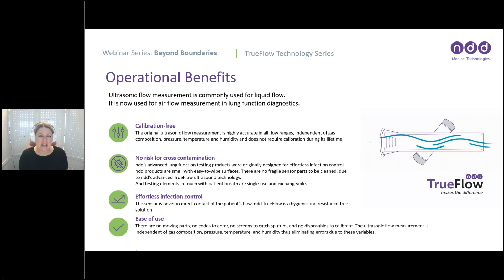There's also no risk of cross-contamination. NDD's advanced lung function testing products were originally designed for effortless infection control. They're small portable devices with easy to wipe surfaces. There are no fragile sensor parts that need to be cleaned or removed between patients due to this TrueFlow technology. The testing elements do not touch or come in contact with the patient's actual breath, so we can use single-use mouthpieces for an effortless exchange between patients. The sensor is never in direct contact with the patient airflow, and so it really is a hygienic and resistance-free solution. Again, there are no moving parts, no codes to enter, no screens to catch rogue sputum, and no disposables to calibrate. The ultrasonic flow measurement is independent of all of those environmental factors that can cause issues in traditional pneumotachs and turbines.